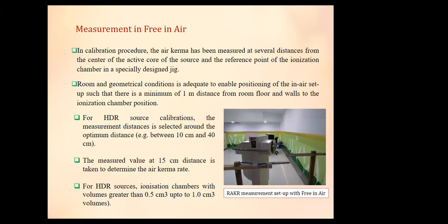In the calibration procedure, the air kerma has been measured at several distances from the center of the active core of the source and the reference point of the ionization chamber in a specially designed jig. The room and geometrical conditions are adequate to enable positioning of the setup such that there is a minimum of 1 meter distance from the room floor and walls, to avoid scattered dose. For HDR source calibrations, the measurement distance is selected around the optimum distance, actually between 10 centimeters and 40 centimeters. In my study, I measured at a 15 centimeter distance to determine the air kerma rate.